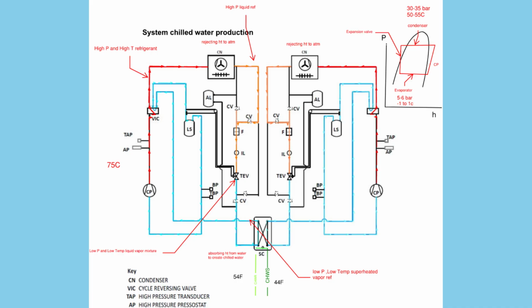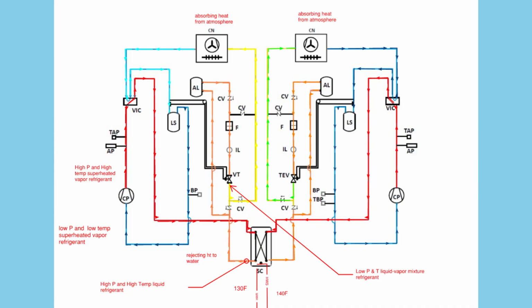The PH diagram and refrigerant circuit with arrow direction for each process explains the whole process. In the diagram, I added typical pressure and temperature values for R410A refrigerant in different working stages. When the heat pump operates in heating mode, the refrigerant circuit shifts roles with the help of the four-way reversing valve. Here's the step-by-step process, where the refrigerant flow in the heat pump in heating mode is indicated with arrow direction. 1. Compression. The cycle begins as low-pressure, low-temperature refrigerant vapor enters the compressor. The compressor raises the refrigerant to a high-pressure, high-temperature superheated vapor. This vapor is now ready to release heat into the water circuit.